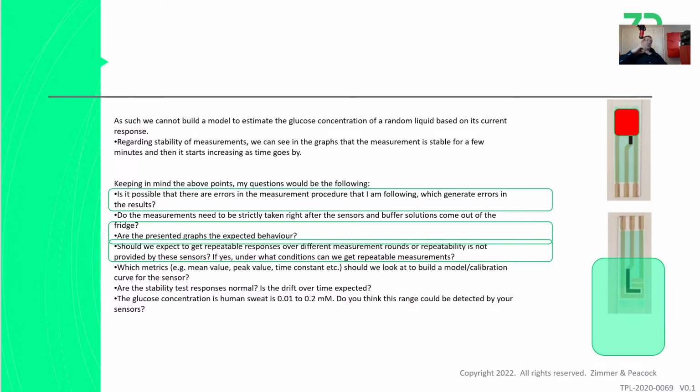If you look at the history of glucose monitors, when they put a glucose sensor into a human body, the first 24 hours used to be really quite bad data. These days they wait 1 hour before giving you data. So they're allowing the sensor to swell and equilibrate. Look at real world CGM sensors, Abbott, Dexcom, Medtronic, and you'll see that they wait something like 1 hour before giving you any results.